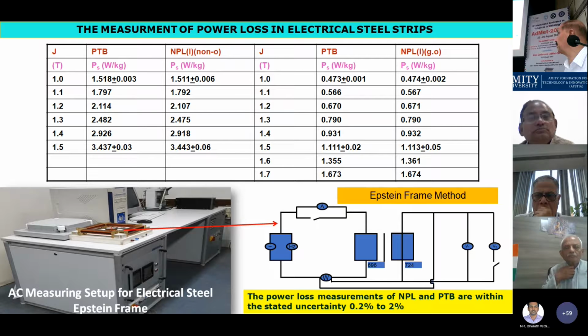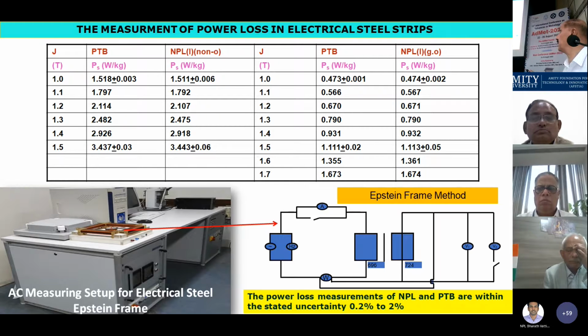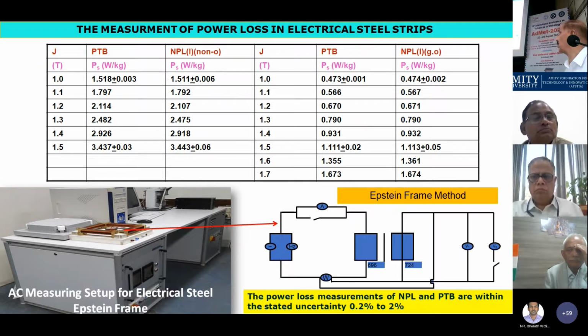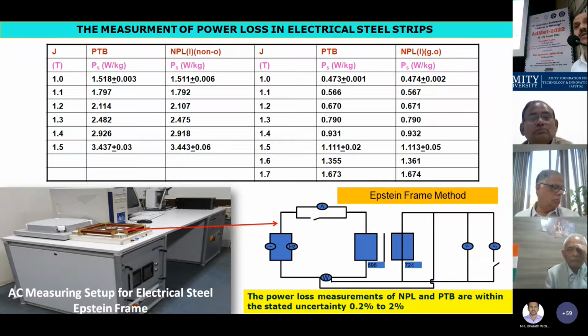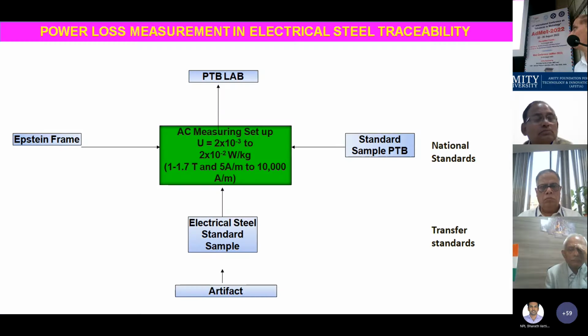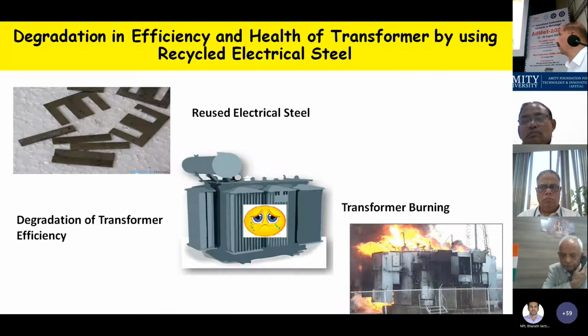The power loss measurements in NPL and PTB are within the stated uncertainty, between 0.2% to 2%. One can see how we have measured the power loss, the static power loss, and then our flux, and the PTB values are here, NPL values are here. That comparison was needed because PTB is another NMI from a developed nation. How do we calculate this? I'll not get into it. A single sample from PTB, a single sheet frame, and then our electrical steel strip sample, and then the artifact. What we do is as a national standard, and then as a transfer standard for the industries.